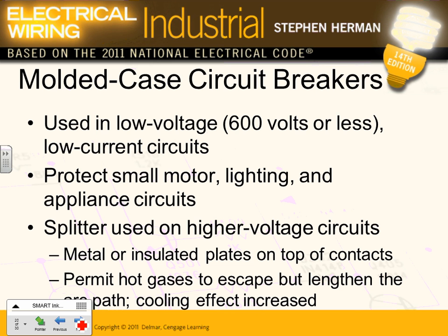Okay, molded case circuit breakers, and again, I'll give you guys a break in a second here. Low voltage, they're 600 volts or less. Low current, typically 15 to, I think, 2500 amps, you can get the molded case. Higher than that, it will be different.